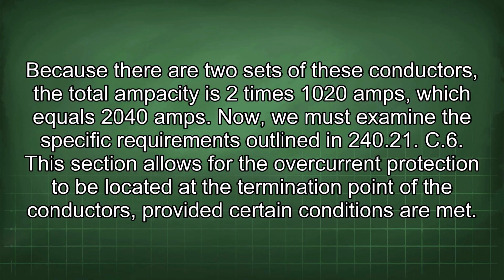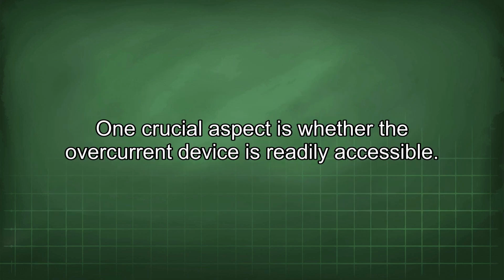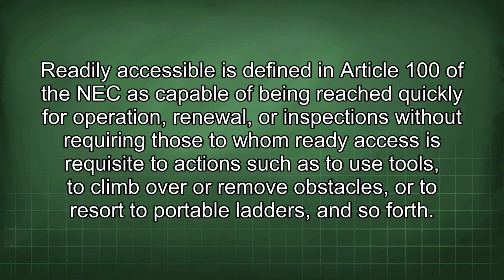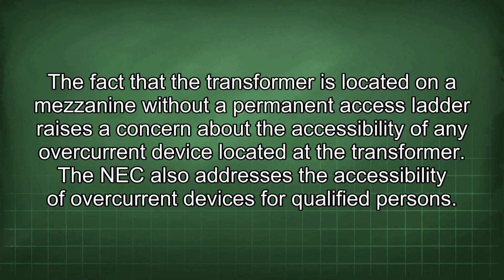Now, we must examine the specific requirements outlined in 240.21(C)(6). This section allows for the overcurrent protection to be located at the termination point of the conductors, provided certain conditions are met. One crucial aspect is whether the overcurrent device is readily accessible. Readily accessible is defined in Article 100 of the NEC as capable of being reached quickly for operation, renewal, or inspections without requiring those to whom ready access is requisite to actions such as to use tools, to climb over or remove obstacles, or to resort to portable ladders, and so forth. The fact that the transformer is located on a mezzanine without a permanent access ladder raises a concern about the accessibility of any overcurrent device located at the transformer.